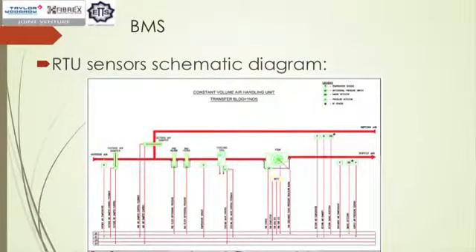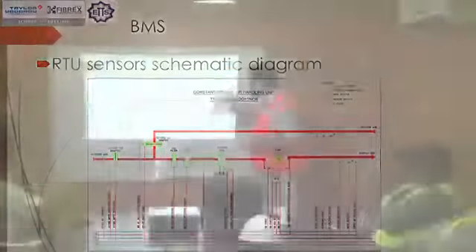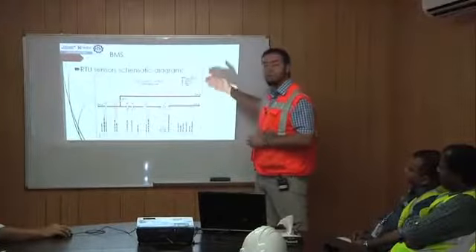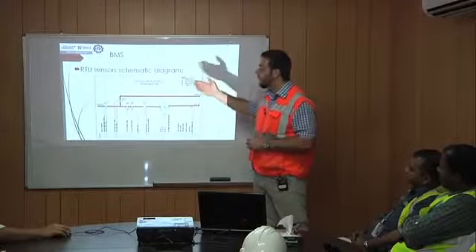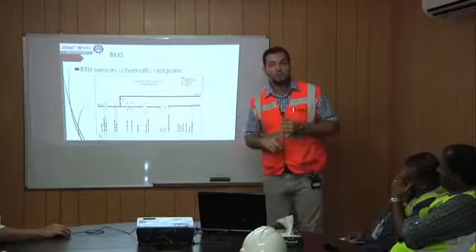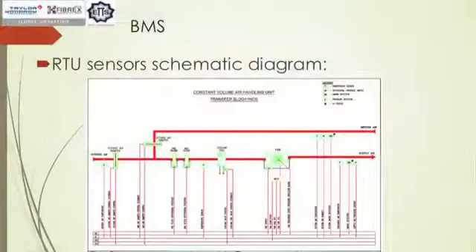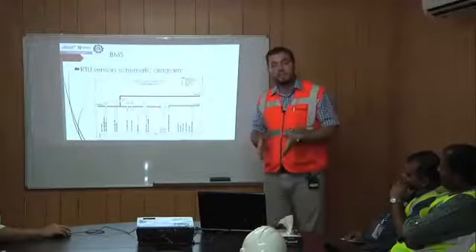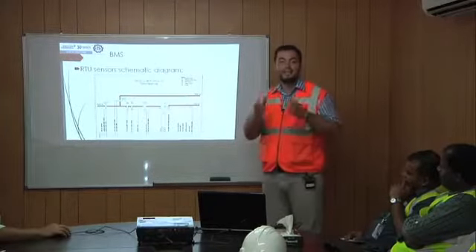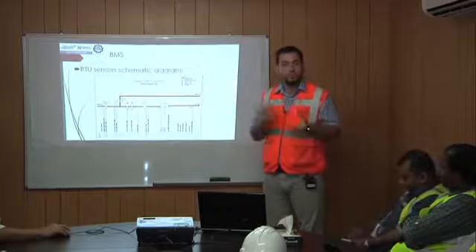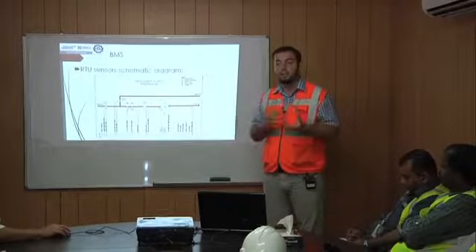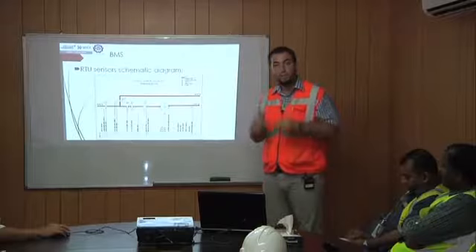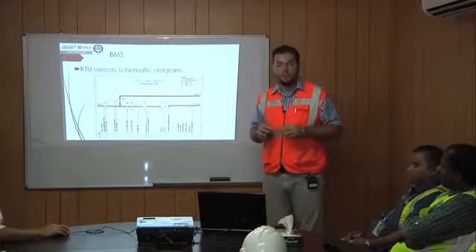So this is kind of a schematic for the RTU unit. We've got a fan, we've got CO, we've got pressure sensors, we've got temperature sensors on the chilled water supply return, we've got temperature sensors on the supply duct, we've got temperature sensor on the fresh air duct, we've got temperature sensor on the return duct. Same goes with the pressure. Also, every section of the RTU has a differential pressure sensor to sense the pressure difference between the 2 sections. This is primarily for the filters.